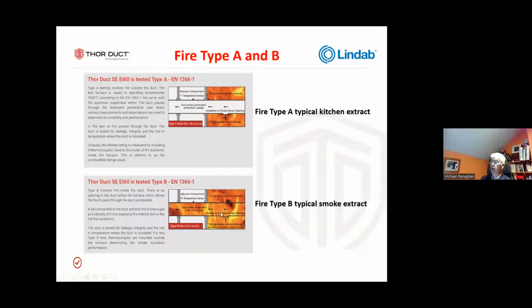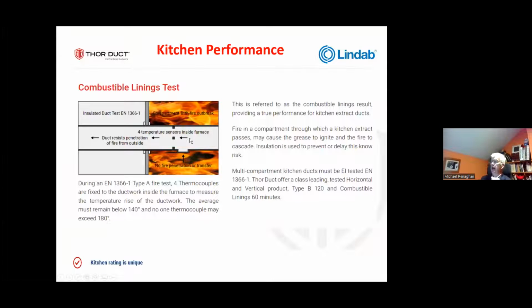The other test is what we call a B test, and the B test is where you have vents inside the duct, and they're actually exhausting the hot gases from the furnace through the duct to the outside, and they're measuring the performance of the insulation. And this, the combustible linings test, which is the kitchen one, is done this way. There's a third test called the C test for leakage. It's very complex, so I'm not going to bother with it here, but just to know that there is another type. It's very similar to the B test.